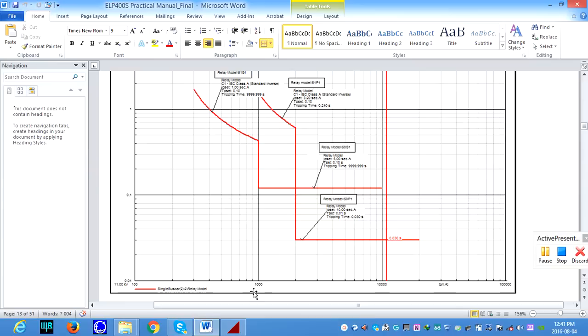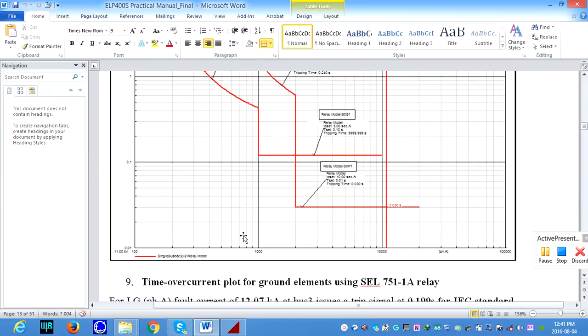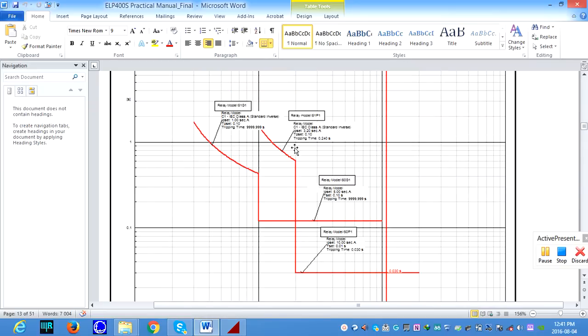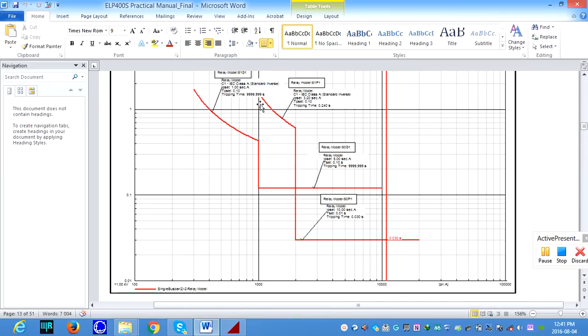That is, you see here, this is your 1000 amperes, and also you must remember it's a time overcurrent plot. It means your current must be in the x coordinate and time must be in your y coordinate. Okay, continue. From 640 to 2000, this is your 2000, this is 1000 and this is 2000. So it means from 640 to 2000, you're going to get an inverse characteristic. Once it reaches the 2000 value, the time will not change, the time will be constant. Okay, from 2000 onwards, the time will be constant in this case.